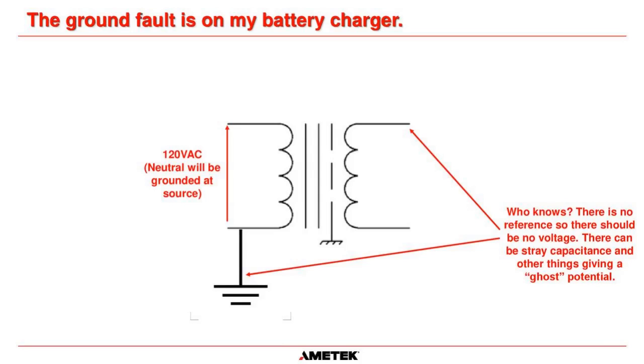I've also seen junction boxes, especially explosion-proof junction boxes. There's a lot of thread, and when you thread the cap down on that box, it can trap a DC cable within that junction box and cause a ground fault. But if it's once per week and it's only for 2 milliseconds, oh boy, I don't know how you're going to find that, and I don't think it's on your charger.